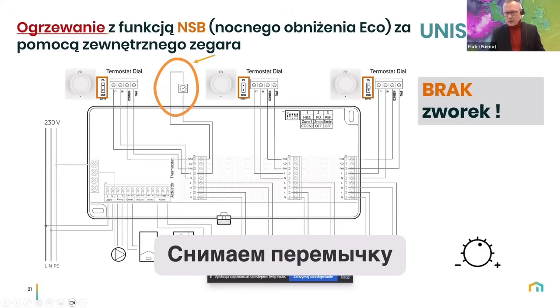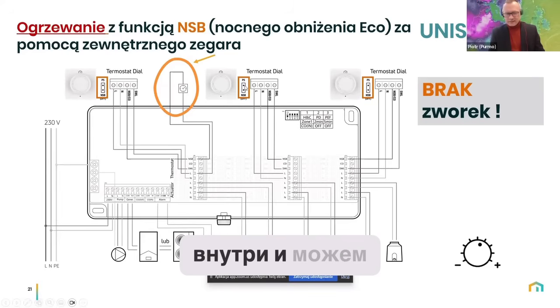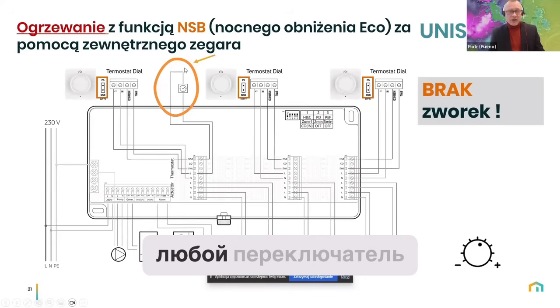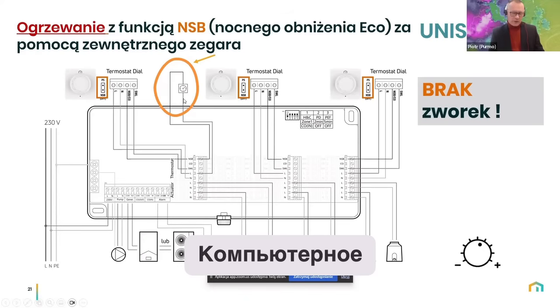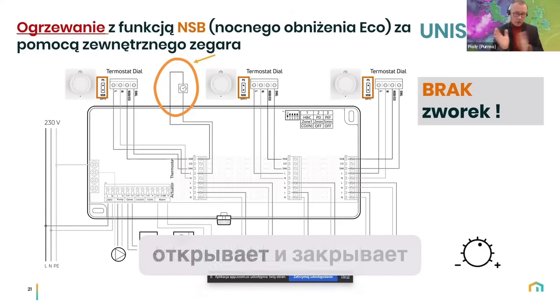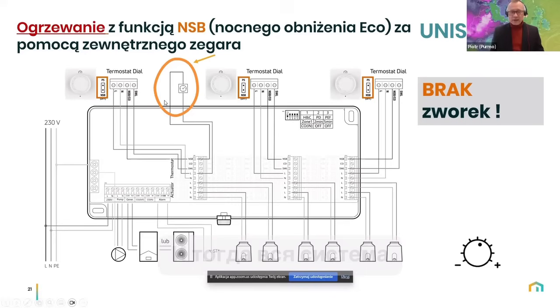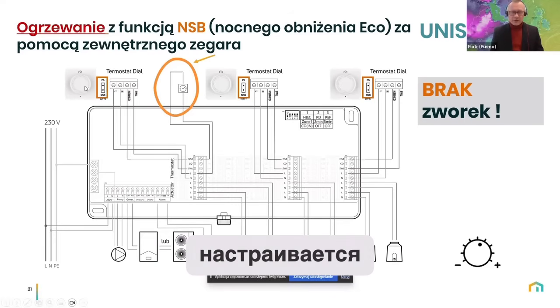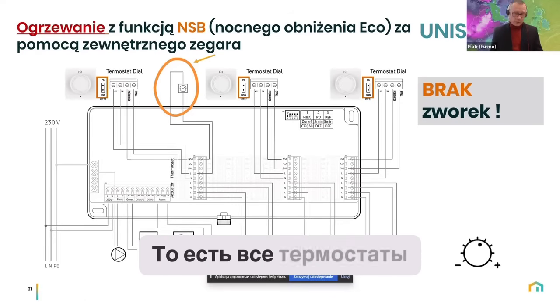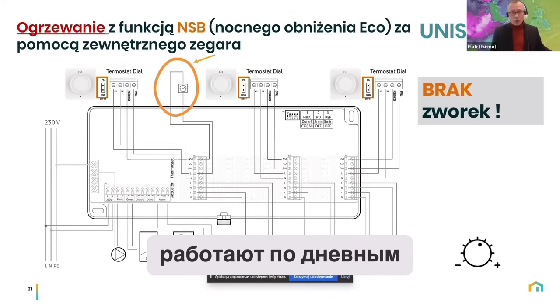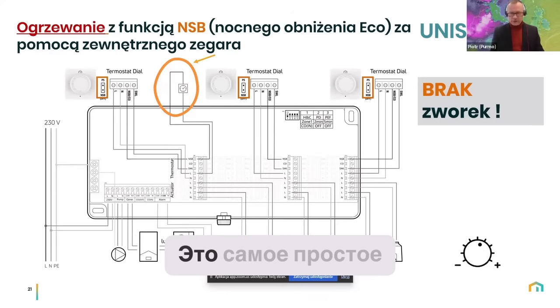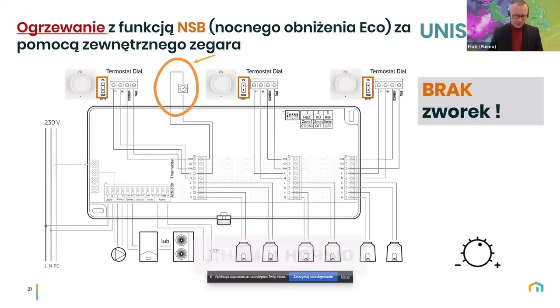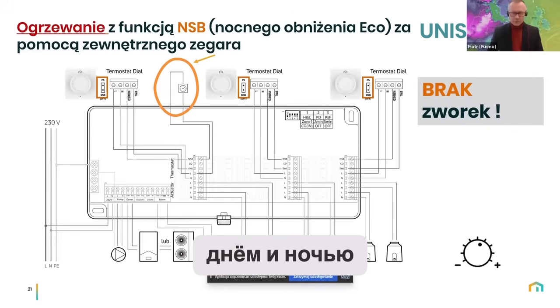We remove the jumper which is placed inside, and we can use any type of switch - it could be computer control, whatever. It is a switch, so it has an open-close function, and then the whole system can be set. It means all thermostats will work according to the night or day settings. This is the simplest and cheapest solution for control of the whole system in day or night.